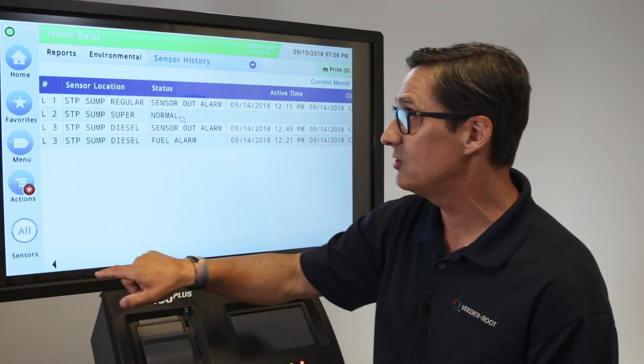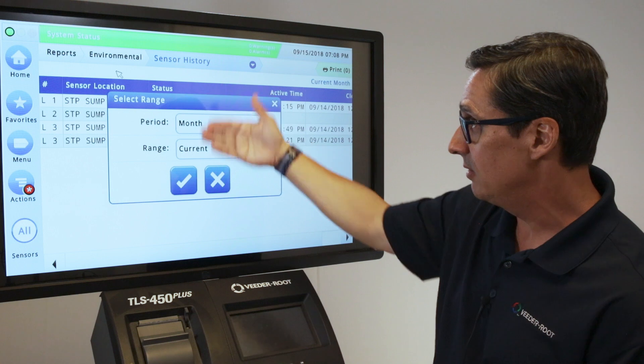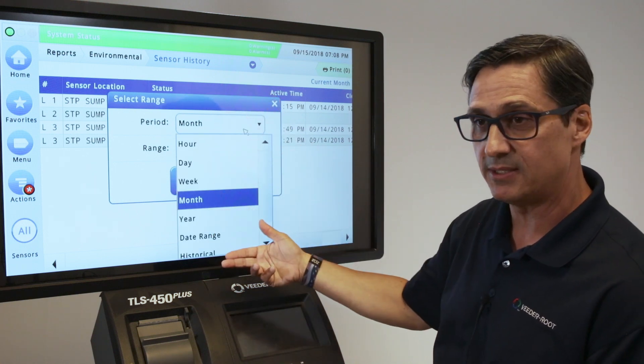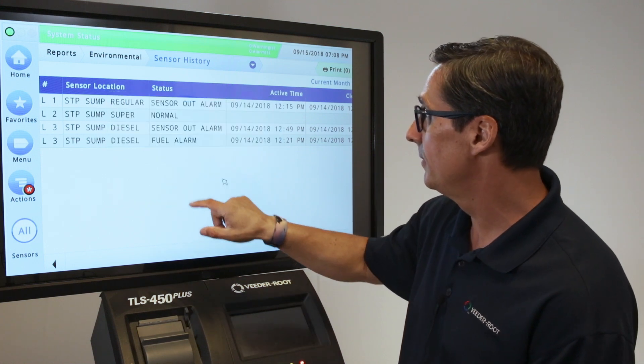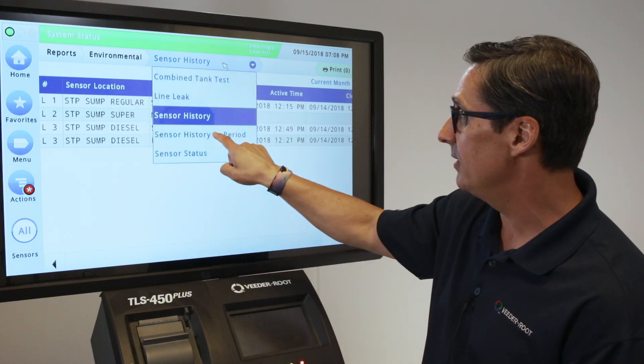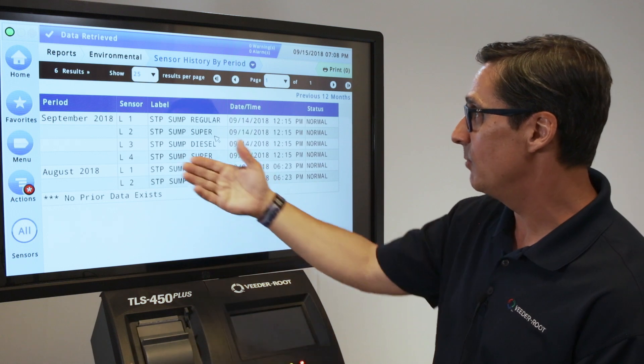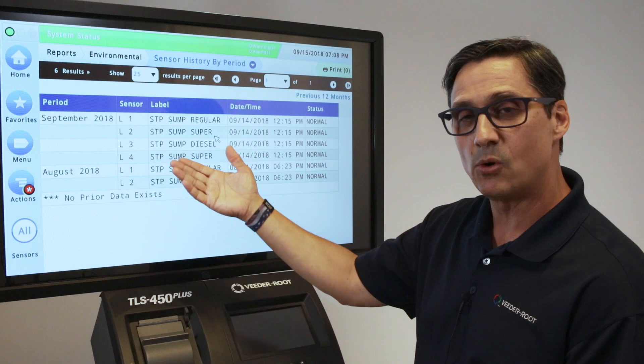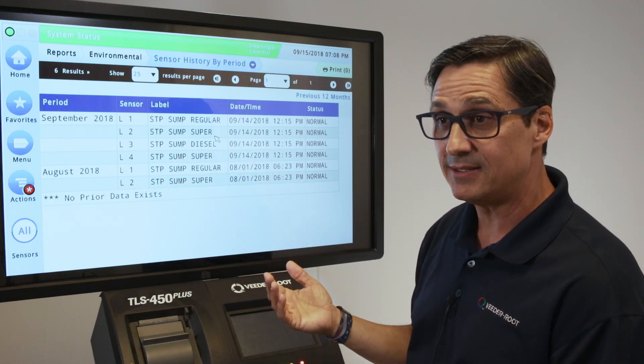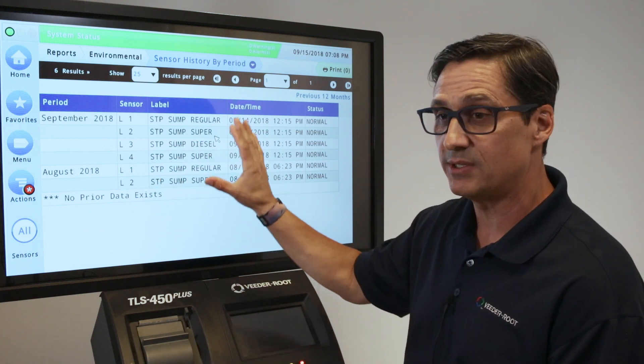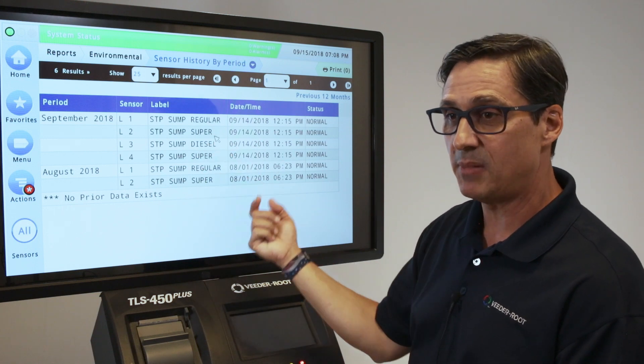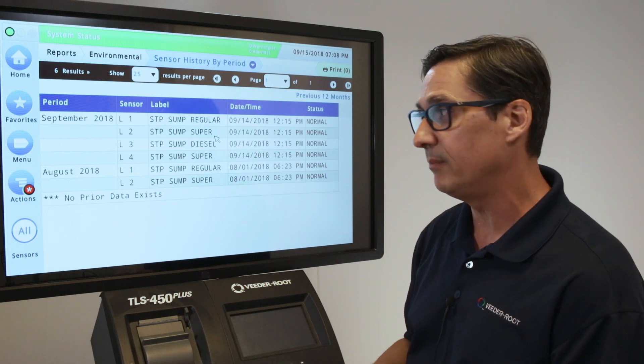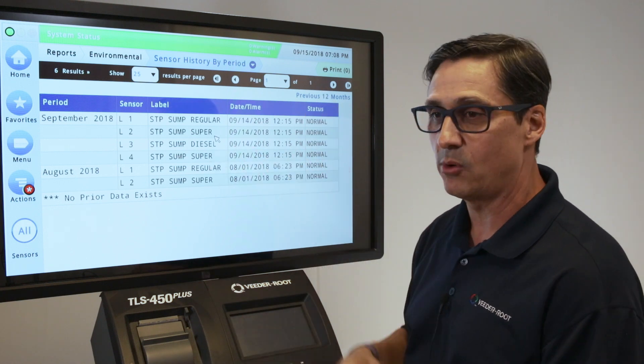Using the Actions button you can select a date range for the report based on various criteria. The last option is sensor history by period, which allows you to get reports based on a specific period. This is common because some states require reports every 30 days, not just monthly. In the setup function you can configure the period to every 30 days so your report reflects that regulatory requirement. You can print this report whenever needed.